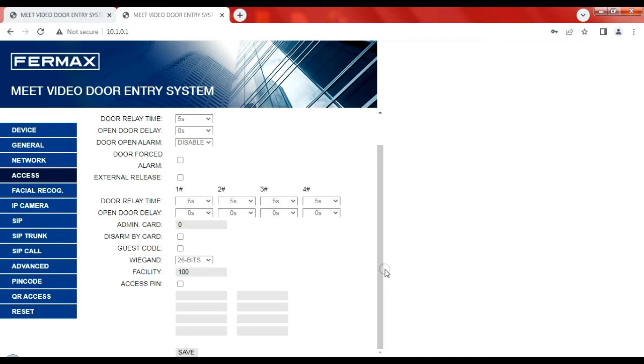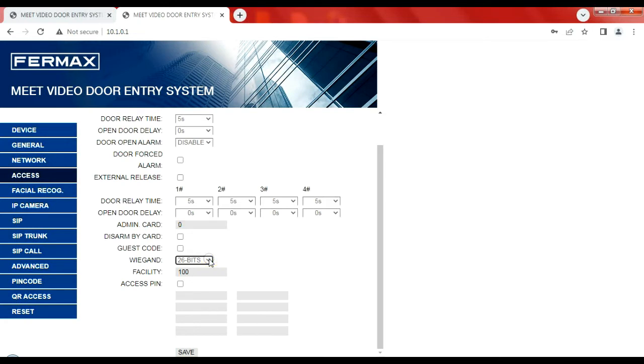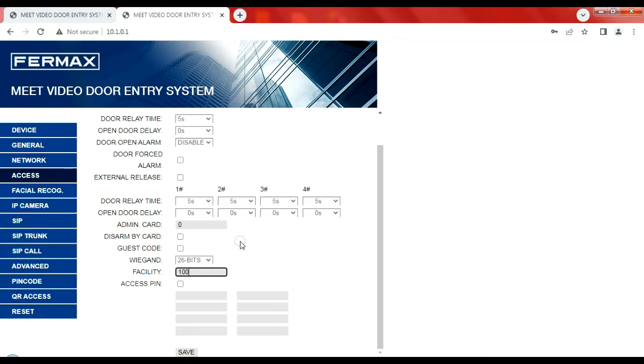If, on the other hand, you're going to be using access control on other doors on the site and you want the built-in MiFare reader to be part of that other system, maybe PAX on a Net2 system, maybe ACT on the ActWin system, TDSI on the EXgarde, WinPak or whatever, any of the systems we do, you can interface it using the Wiegand interface, using the 26-bit Wiegand output. The next one down is the facility code. If you're using 26-bit Wiegand, sometimes you'll be putting the site code, the facility code. So that covers this field here.